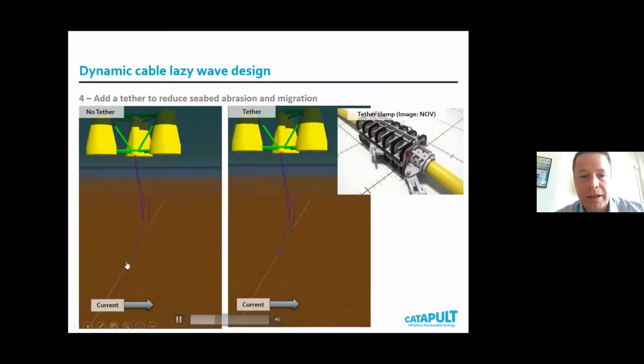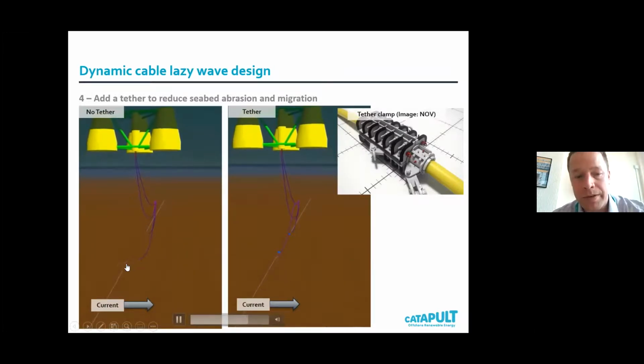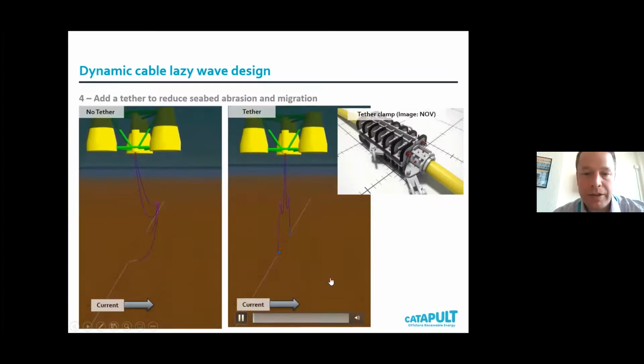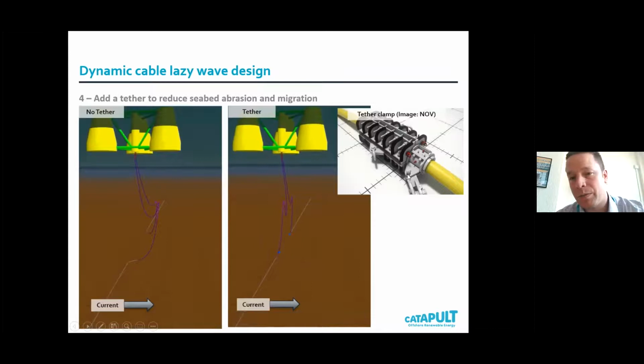So what we'll see is that in many cases with relatively high currents or even moderate currents like you see in the North Sea, our cables move a lot. And that's a problem because it means that the cable is going to be dragging on the seabed, it's going to be wearing on the seabed, and eventually it might migrate out of position. So it's really not a good thing for this to happen. So a solution to this, which we see in a lot of cases, is tethers, which are basically clamped and then tied back to the seabed with some wires. And that stops the cables moving too much. So it limits how much they can move sideways and also forward and back with the current. So that's a solution that's very often used.